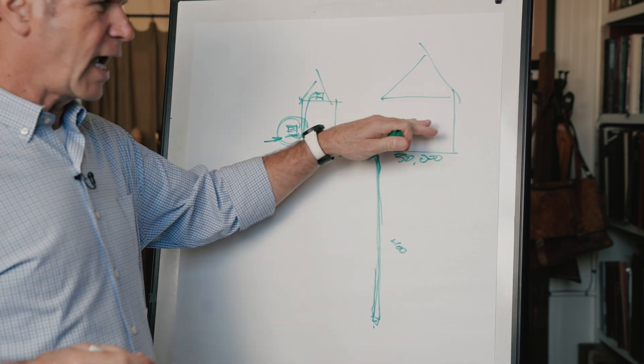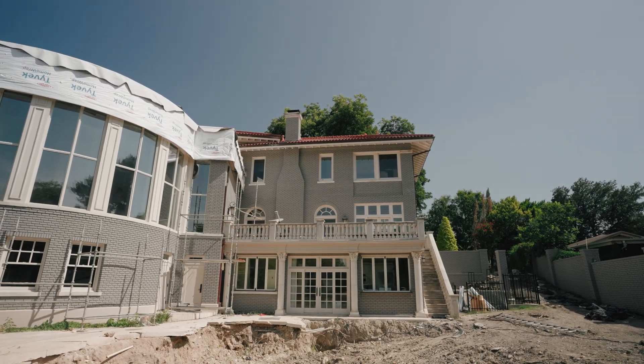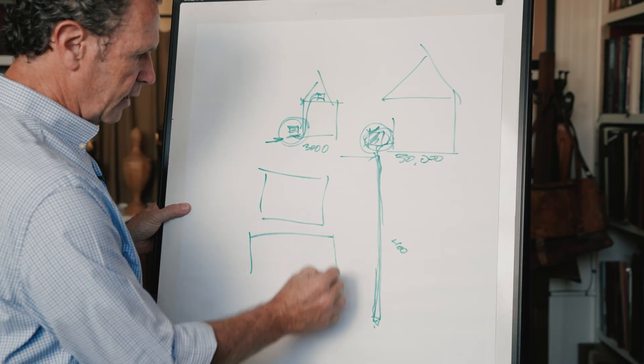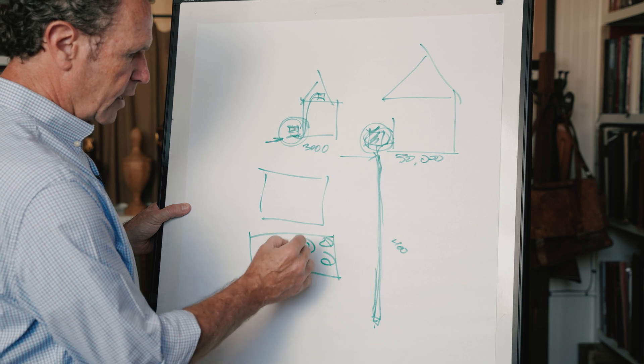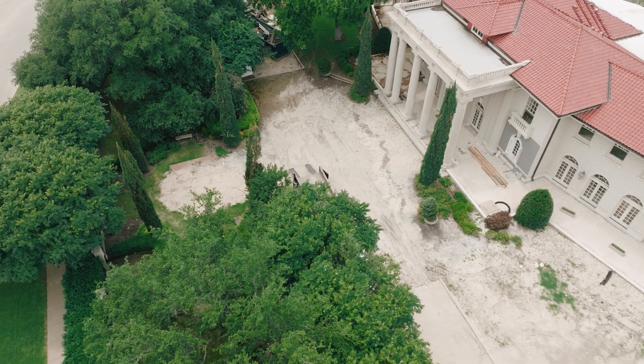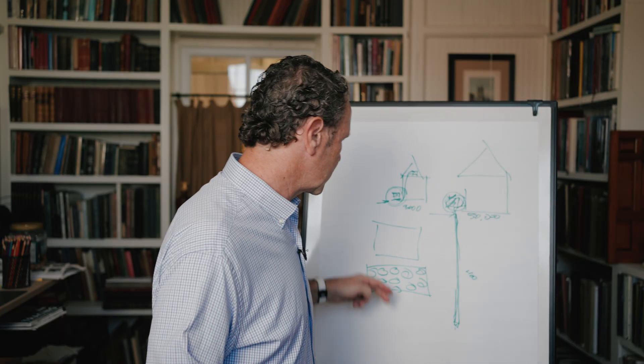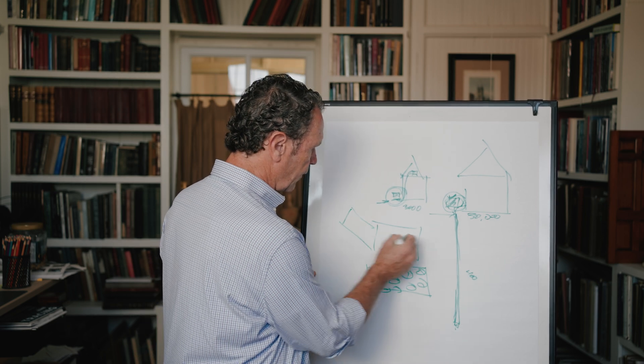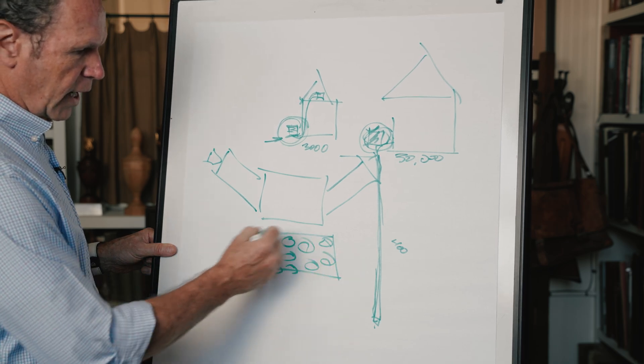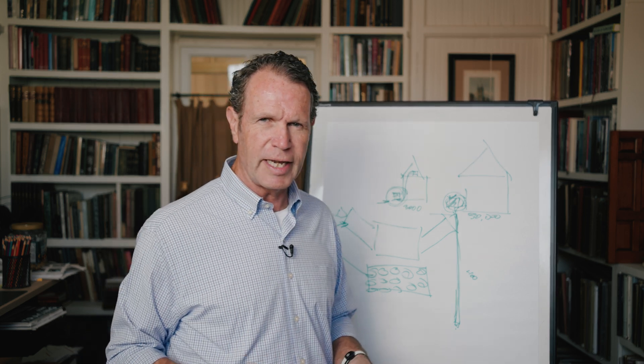My property has no compressors. The Italian Revival house — the big chiller we had on the side is gone. If you look at the front of that house, the driveway area is where all our holes are drilled. These holes are five-inch holes, about 10 to 20 feet apart — like a little water well hole — and one-inch lines run down into the earth. Here's our Italian Revival house, and our old chiller system was right there. We now have these pipes over the front driveway that we'll cover up, all running to the system in the basement, and it runs much more efficiently.